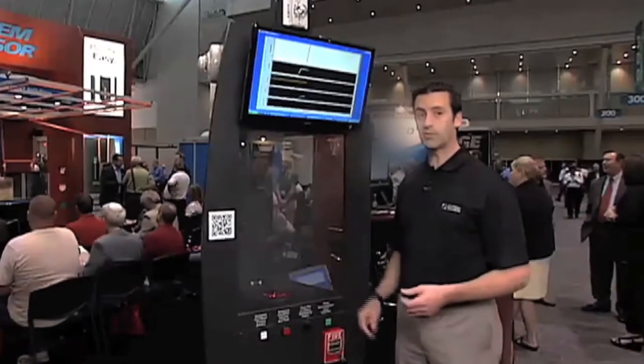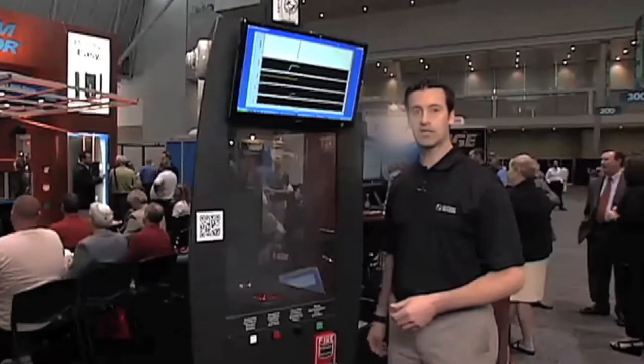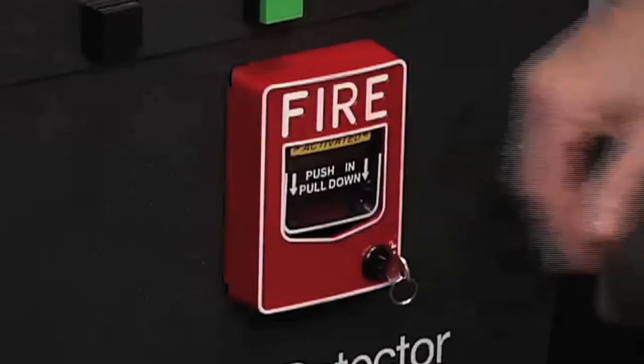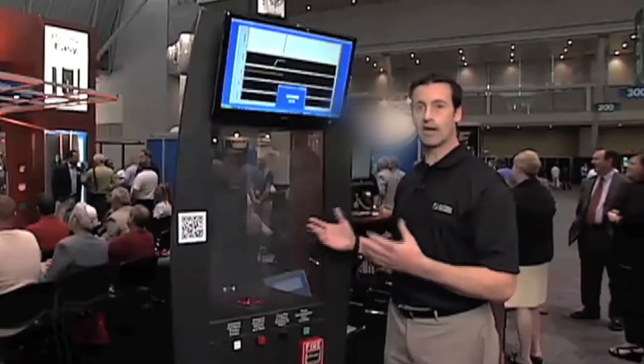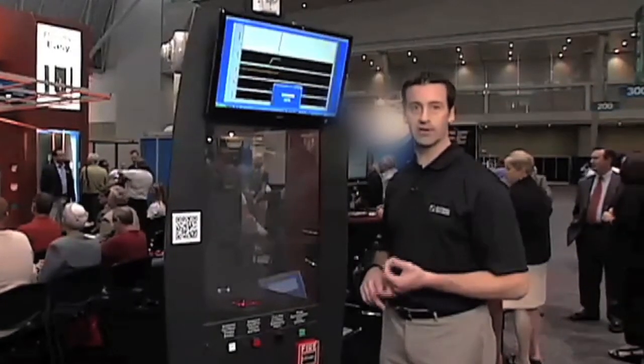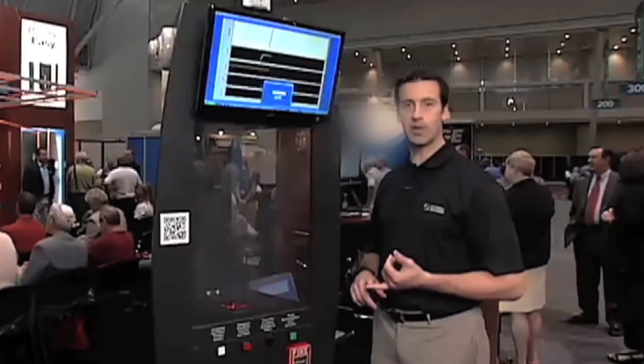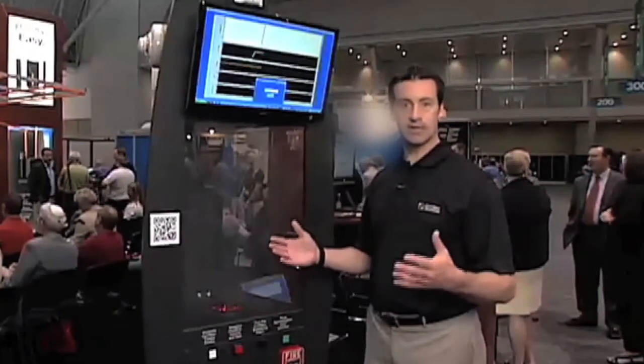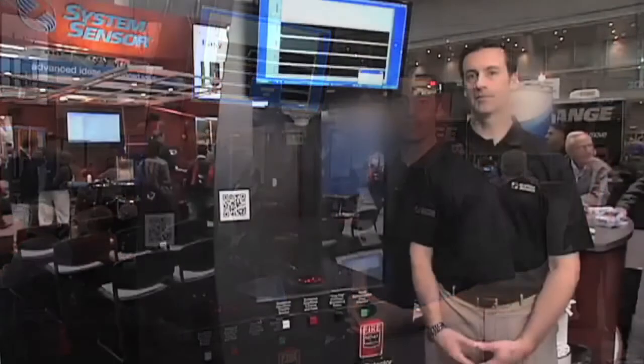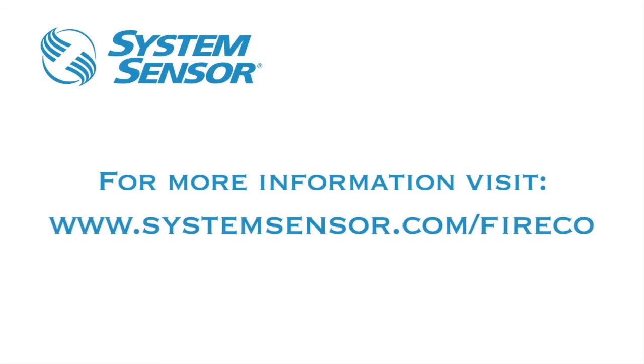However, if we did have a real fire event elsewhere in the facility, or if we set up the system to evacuate on all conditions, we can again simulate that by pulling the pull station — turning on the entire building's horns, strobes, and sounder bases throughout the facility in full synchronization using the System Sensor synchronization protocol, providing a clear NFPA 72-compliant communication of the alarm event, all synchronized within the notification zone. Thank you for watching this demonstration of our new fire-CO product. For more information go to www.systemsensor.com/fireco.